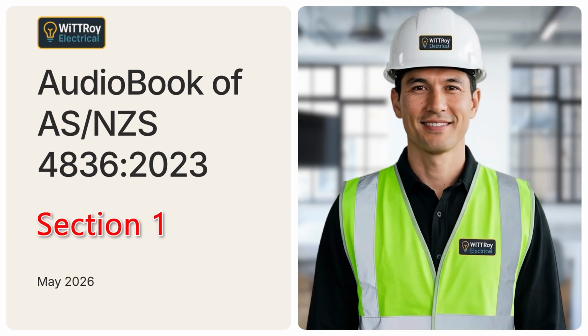Clause 1.4.41.1. Extra low voltage. Extra low voltage, or ELV, means voltage not exceeding 50 volts AC, or 120 volts ripple-free DC. Even though ELV is lower than low voltage, it still needs safe working practices, especially where other hazards are present.